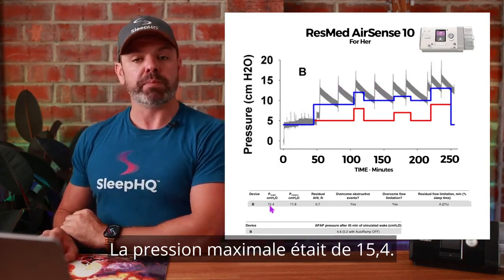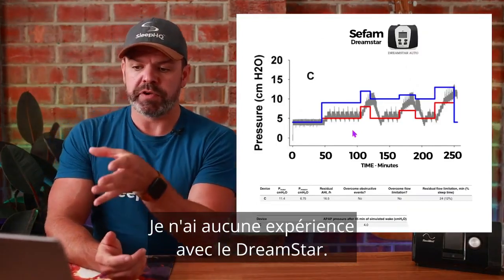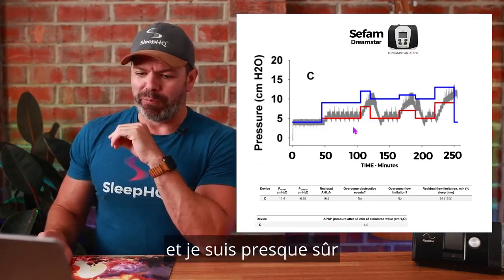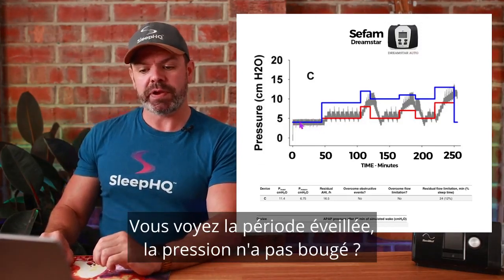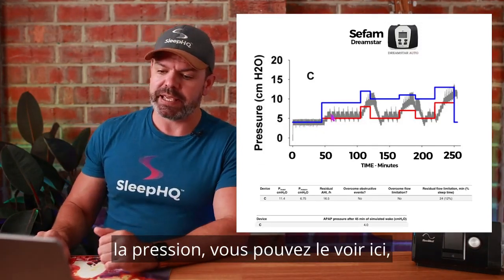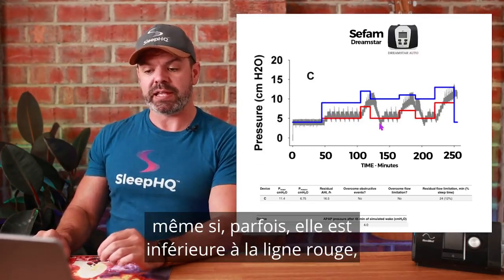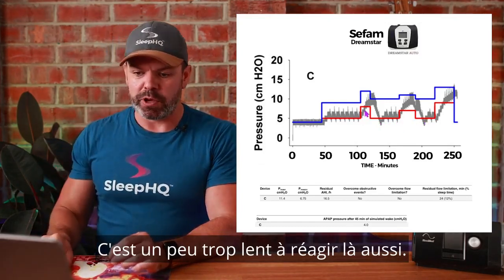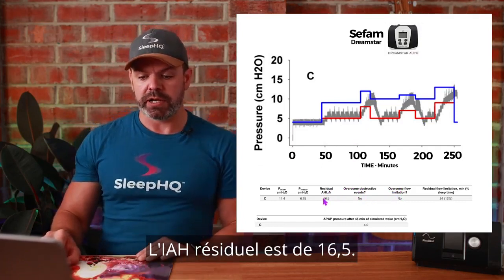Next up, the Sefam DreamStar Auto. I have no experience with the DreamStar, but I do have a Sefam S.Box — I believe they're a French company with pretty much the same algorithm. Not a great algorithm. They do an exceptionally good job during the wake period — the pressure barely moves — but once sleep arrives the pressure just isn't reaching breathing normalization. It's only controlling obstructive apneas, and even then sometimes it's below the red line. Residual AHI: 16.5. That's a fail.